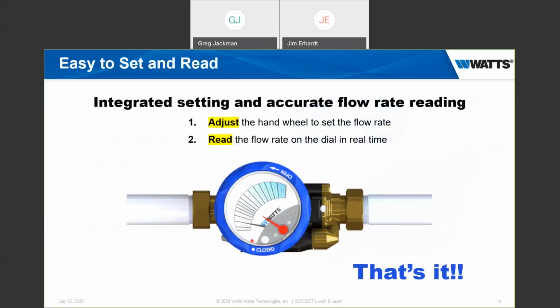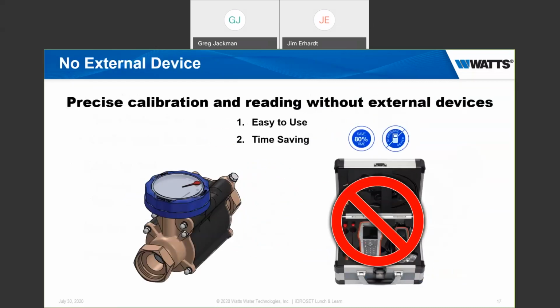So to adjust, to set our flow, it's very simple. We adjust the hand wheel to the required flow rate, whatever that might be, and we can read the flow right off the dial. That's it. That's all there is to it. So we're going to show you a video coming up here, which kind of does a side-by-side of balancing with the iDROSET versus balancing with a standard circuit setter using a digital manometer. You can imagine it's going to be quite a difference in the time taken. So precise reading without external instruments, easy to use, time saving.